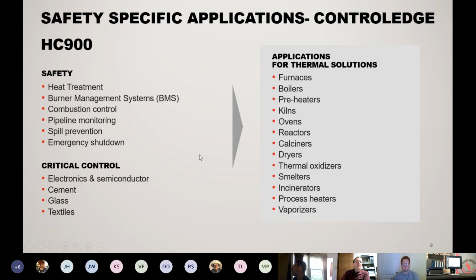When we get down into some of the safety applications, like I talked about earlier, the burner management system, using an HC900 SIL-rated burner management, would be a pretty good example of a safety type system that you would want to use the HC900 in. Combustion control, pipeline monitoring, spill prevention, emergency shutdown. We're actually using the HC900 for not only process safety, but also for personal safety within plants as well.